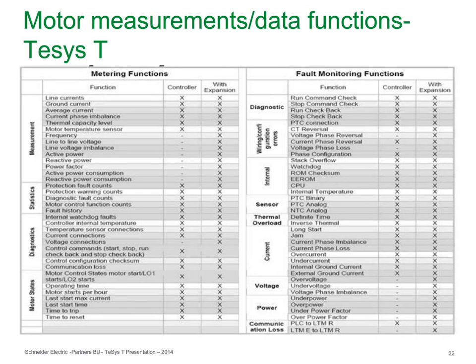But maybe even more useful is the fault monitoring functions here of what things can I actually detect that would help me identify either alarms or faults that would allow me to do maintenance based upon the fact that I know how to fix it before I have to make the trip. And again, we've got things here, if I look at, say, the current: phase loss, phase imbalance, jam, long start. Or on the grounding side, which can be very important for processes, is having the capability to know, is it an internal ground current, an external ground current? Do I have an undercurrent or an overvoltage? These all are very, very useful from a standpoint of identifying grounding problems. And grounding problems can be some of the most nagging issues in keeping a process up and running.